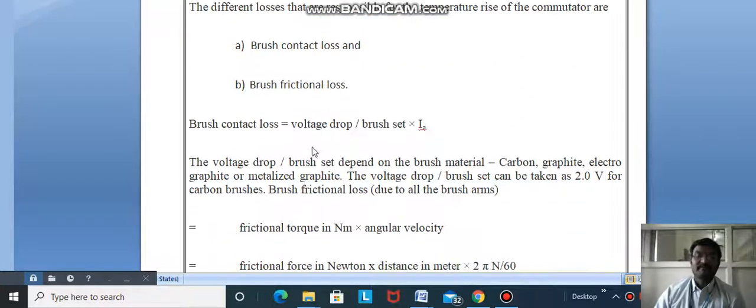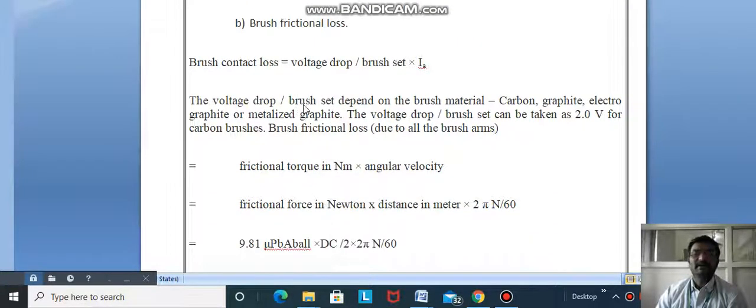Different losses are responsible for temperature rise: brush contact loss and brush frictional loss. When the motor rotates, frictional losses occur. Brush contact loss equals voltage drop per brush set multiplied by armature current Ia. The voltage drop per brush set depends on brush material: carbon, graphite, electro-graphite, or metalized graphite.